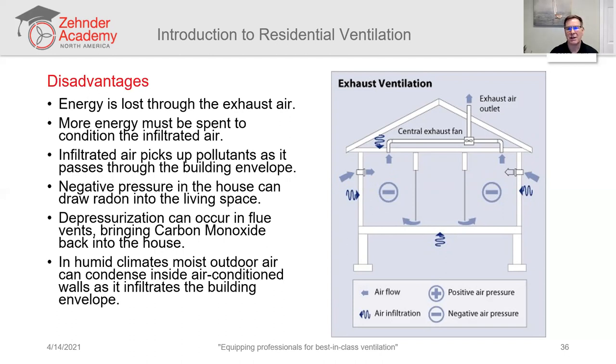What are the disadvantages of this? Well, of course, you're exhausting out conditioned air for most of the year. So whatever energy was spent on conditioning that air is going out the stack and contributing to the local microclimate. Of course, you've got to spend more energy now to condition that infiltrated air because that didn't get conditioned on its way in either. Infiltrated air can pick up pollutants depending on where it's coming from. So again, if you had some very deliberate inlets and you had a filter on there, that might be a good idea. But typically that's not done.